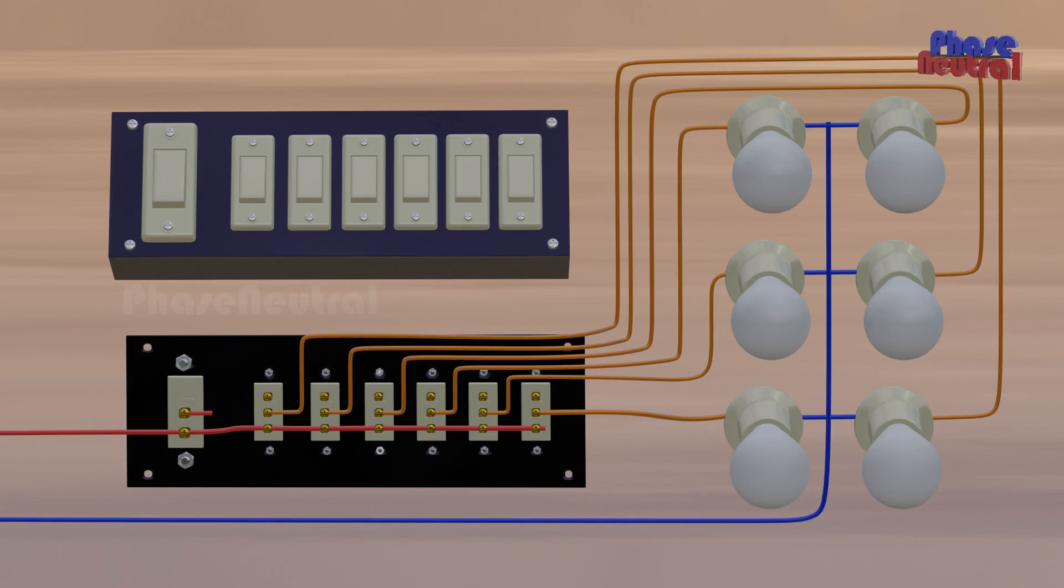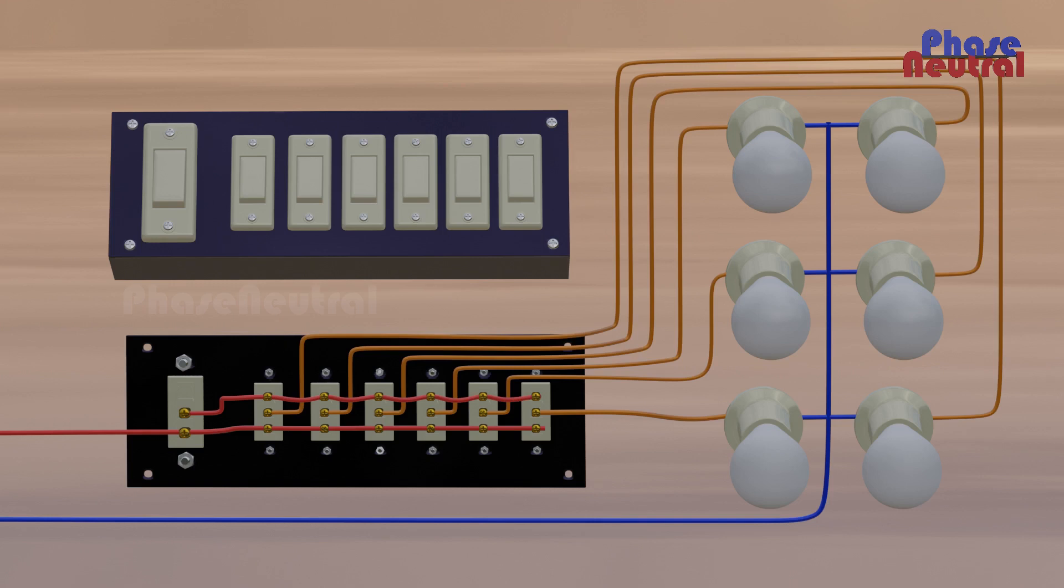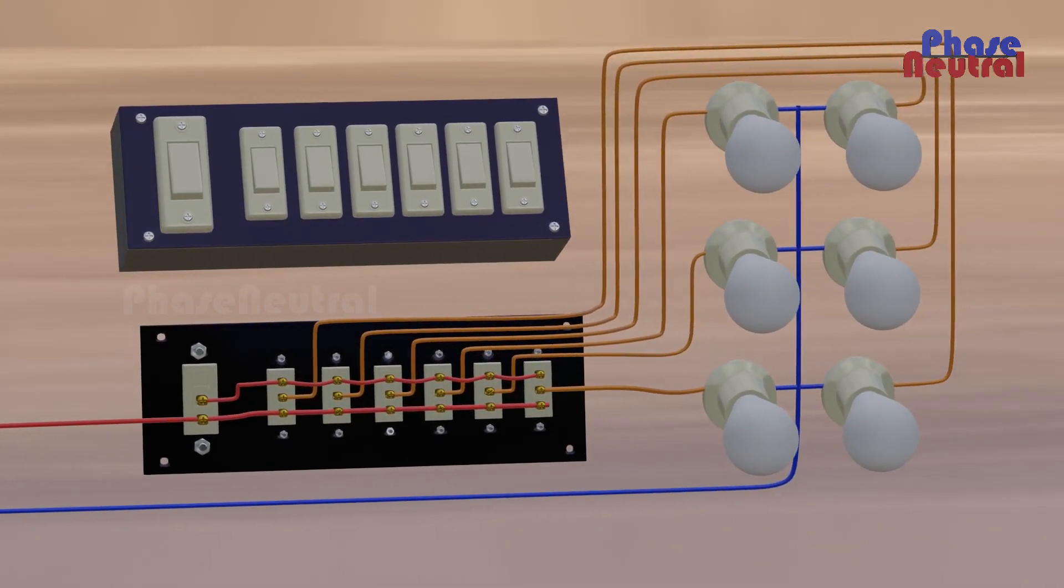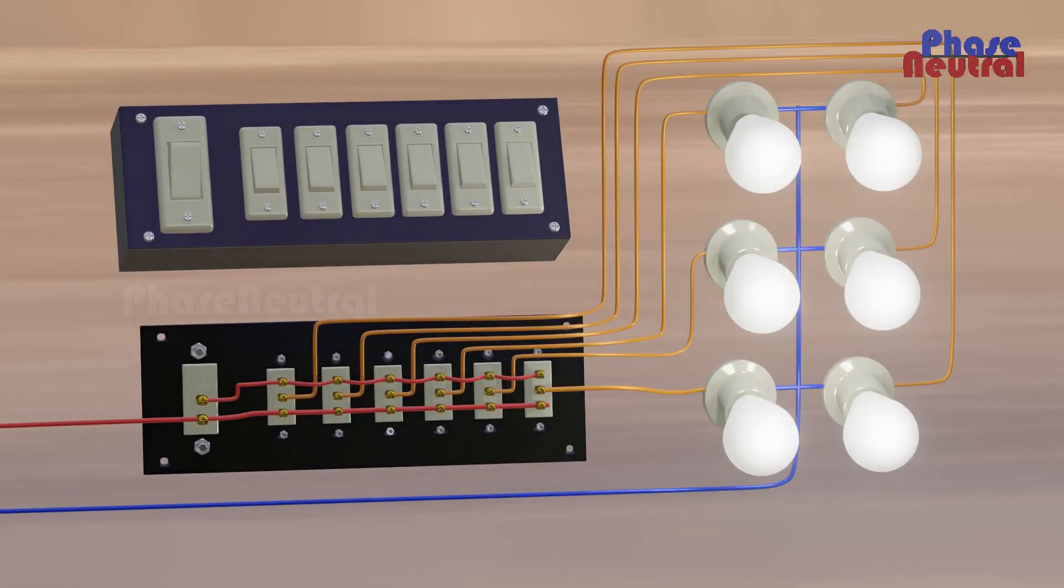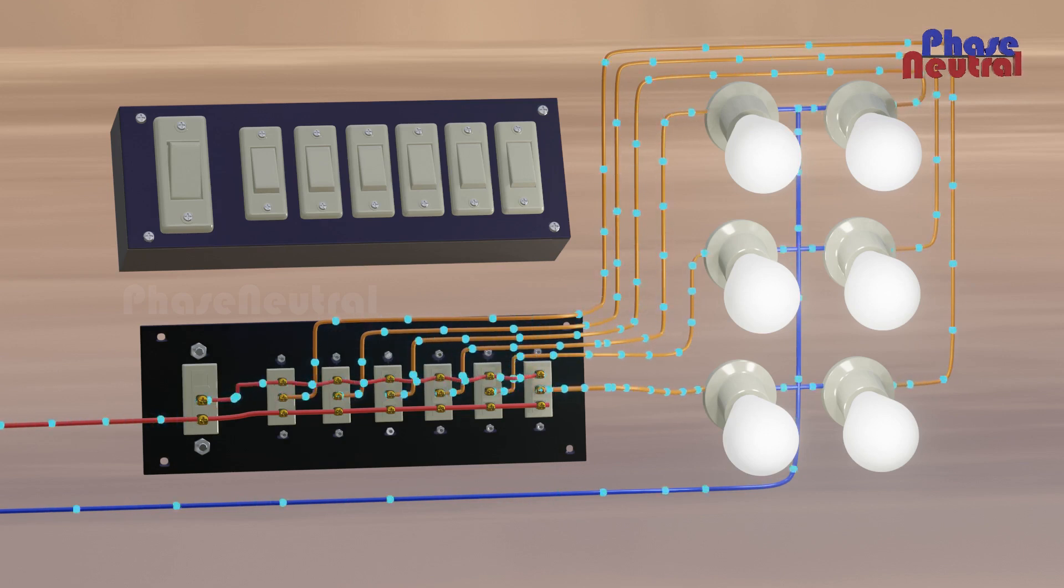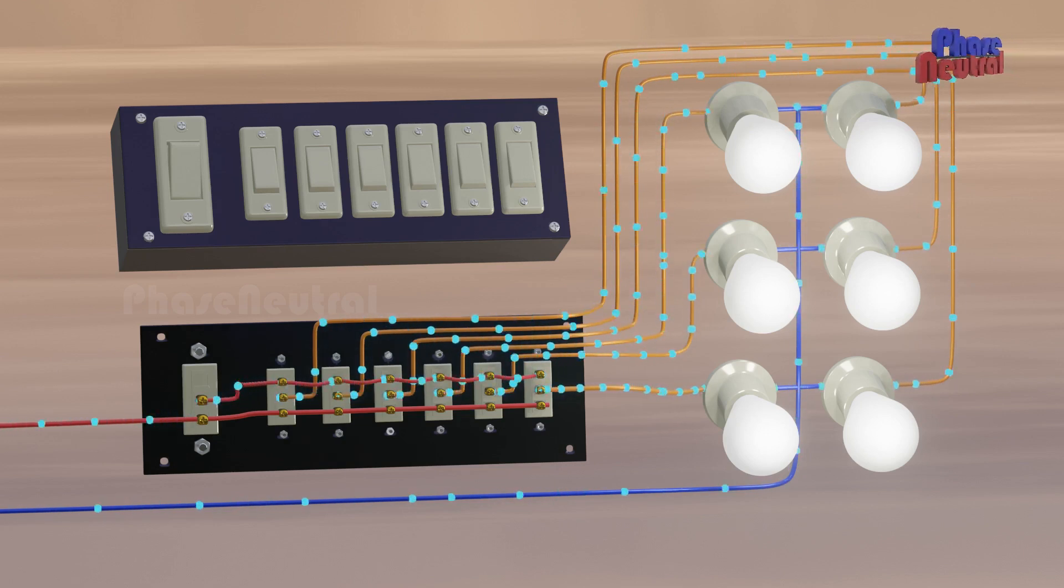Next, we connect another point of the master switch to the L1 point of all two-way switches. When you turn on the master switch, current flows through the master switch to L1 of every two-way switch, and it flows to the bulb through L1 to common point when the two-way switches are in off position.